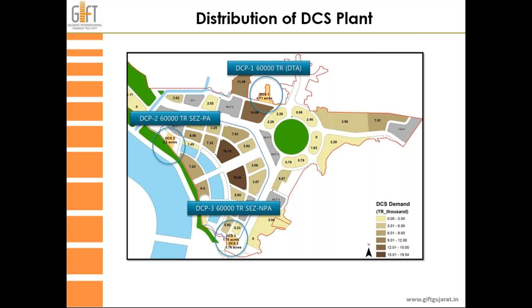This is the first phase development GIFT has done. We have a first plant of 10,000 ton with 10,000 ton-hour TES tank. We have laid the DCS chilled water network of 4 kilometers, which is operational right now, and the pipeline is laid under utility tunnels. You can see in the pictures the DCS pipes laid in a utility tunnel. This is, I think, a first of its kind installation.